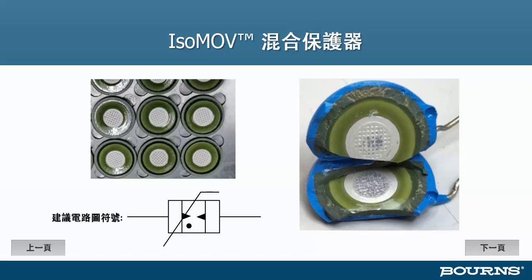The second picture shows a finished IsoMOV device that has been intentionally broken apart. You can see the blue epoxy coating on the outside, followed by the black MOV material, followed by the green glass, and then the GDT area in the center. The diagram at the lower left shows a suggested new schematic symbol to represent this hybrid device. There is no accepted symbol for this in the industry, so we're just suggesting this as a possibility.